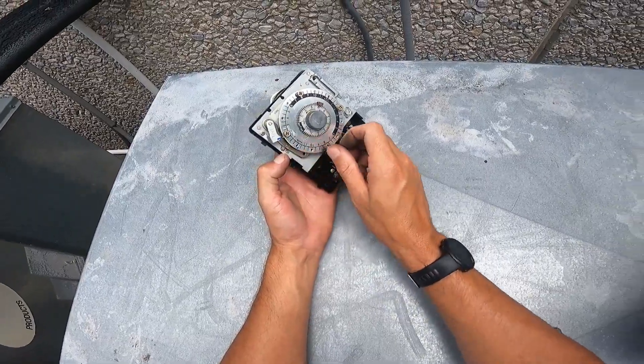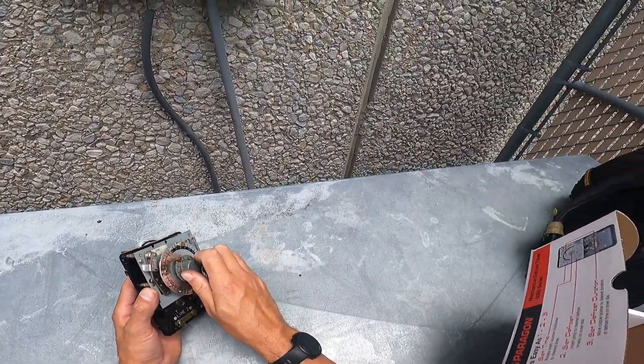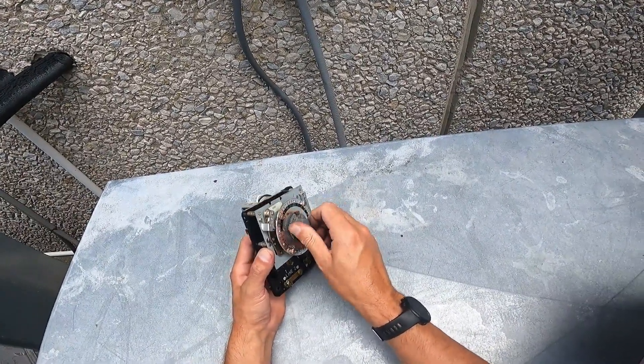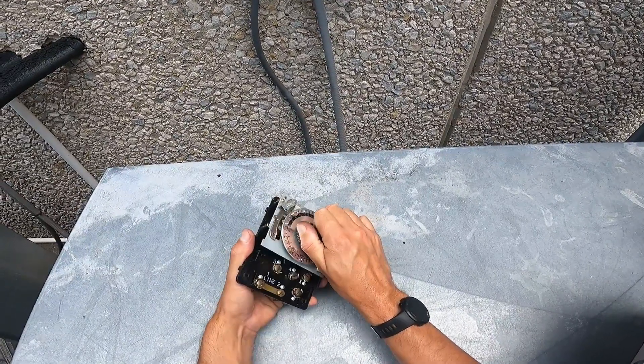The temperature they're trying to maintain is 36 to 46. When I got here, this unit was right at the edge of a defrost. It took all the old man strength I had to push it into and out of that defrost, but then it started rolling fine on its own.